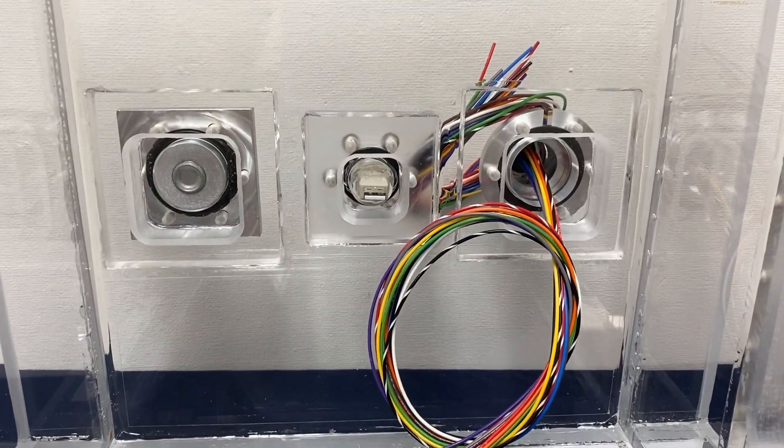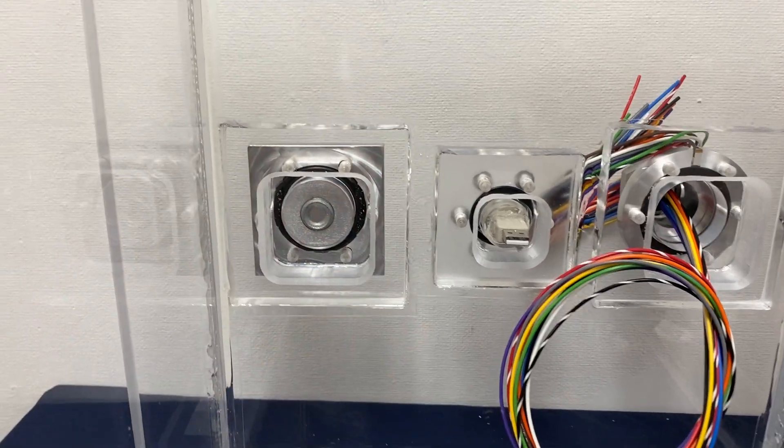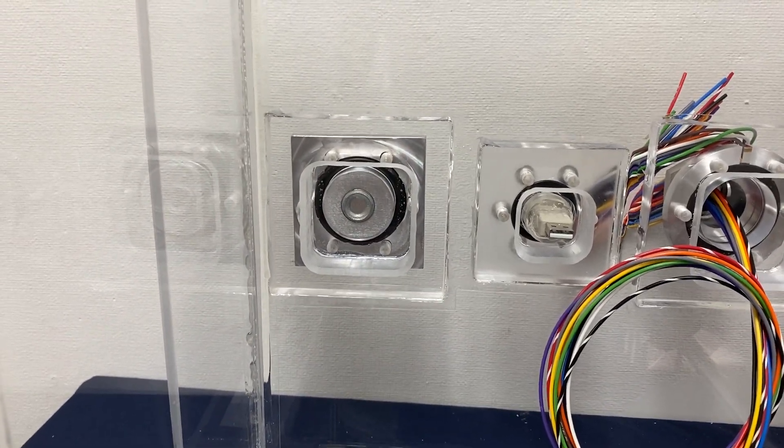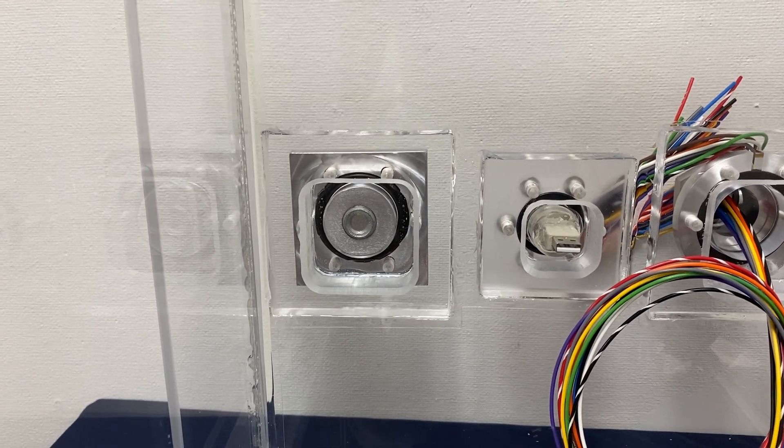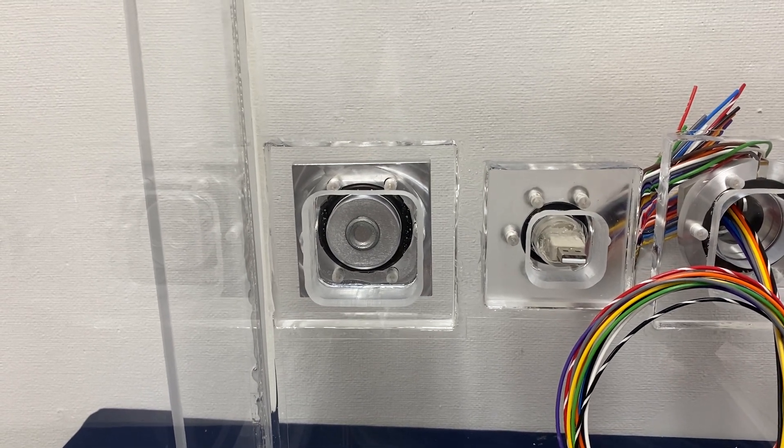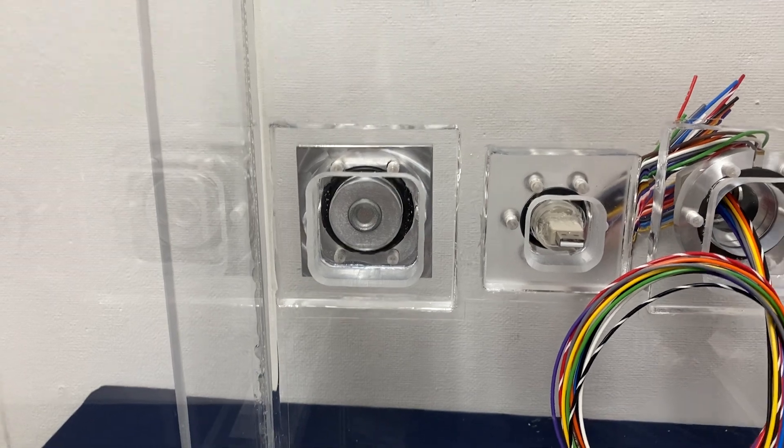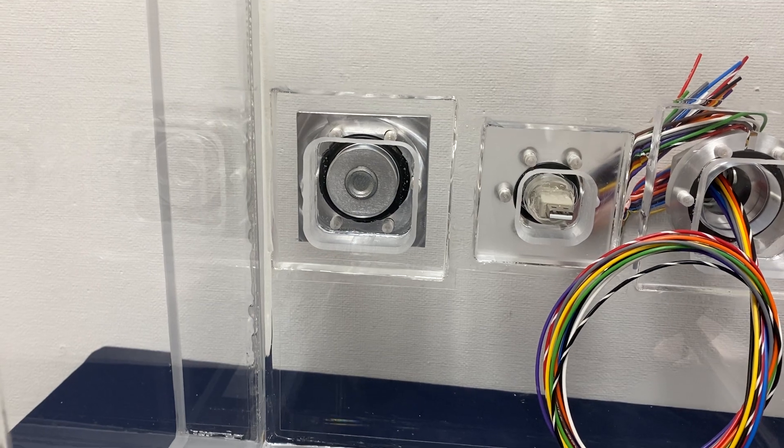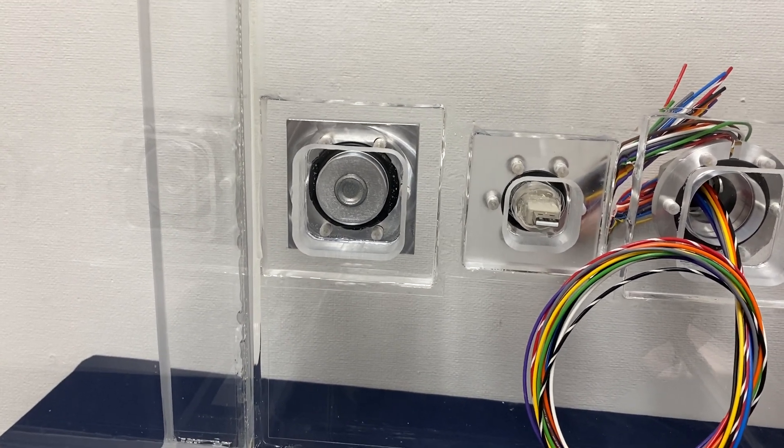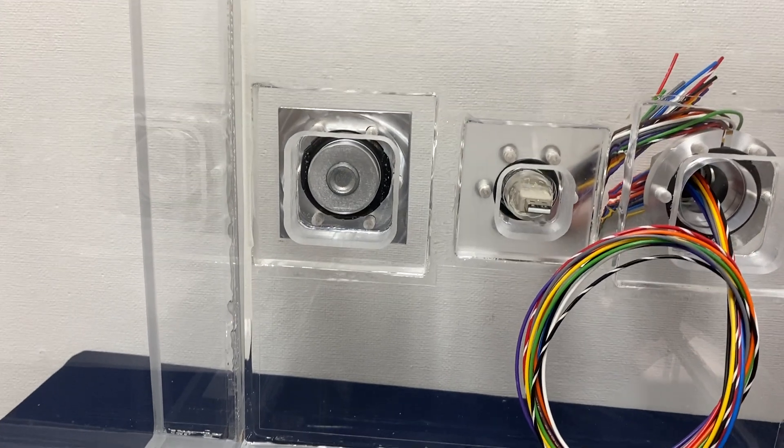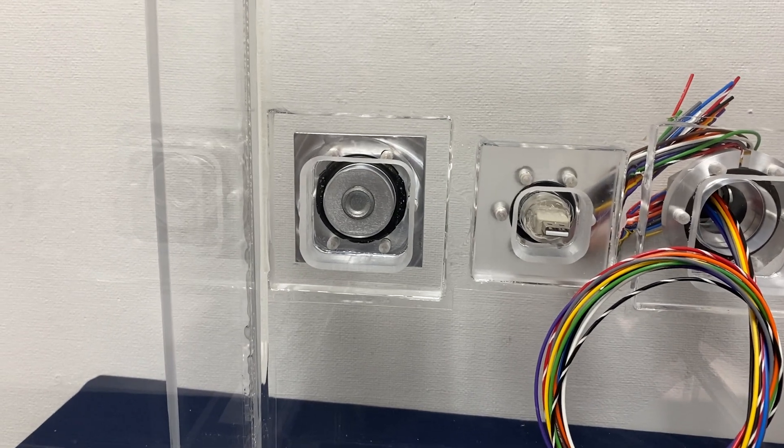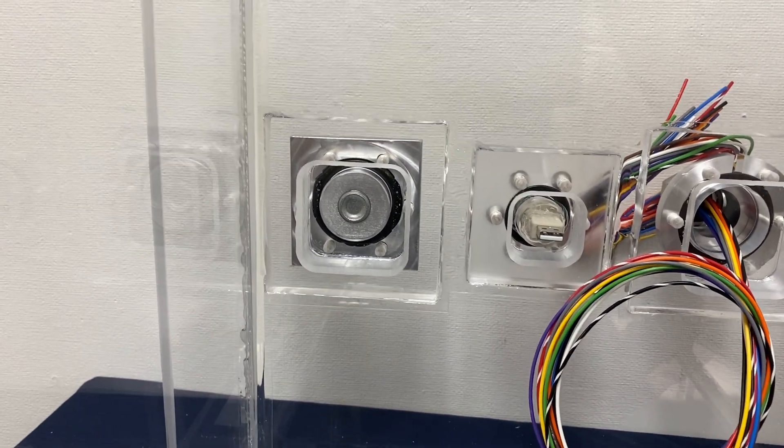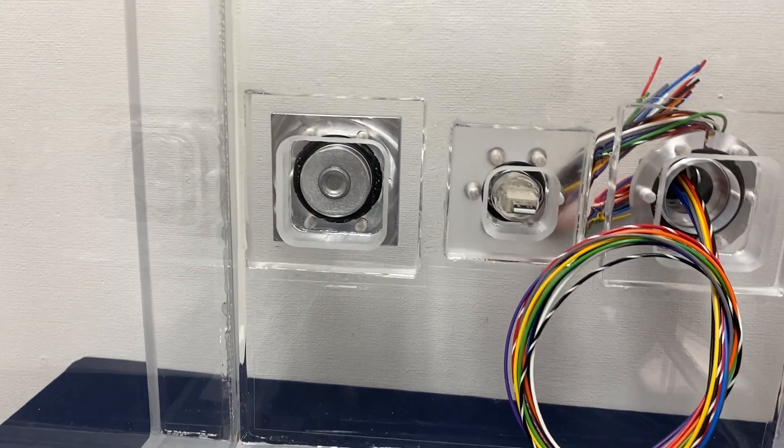And the third feed-through is a threaded feed-through, meaning that this is a custom thread. The reason that we have it this way is that we do not thread into the acrylic. Acrylic is not meant to be sheared, and a thread and a bolt will generate shear to the acrylic, and that creates crazing and stress crazing, which is not good for the vacuum and could also create a potential for leaks. So the way that we mitigate this issue is that we anchor a metallic plate and then we thread that metallic plate so that there is no threading done to the acrylic—we just thread the metallic plate.